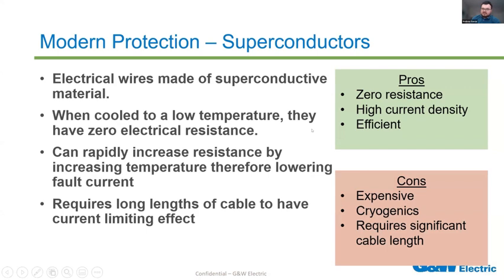So a fraction of the cable size and weight, you end up using smaller poles, and it ends up being less expensive. But the cons overall are that these are a lot more expensive than a regular conductor. Superconductive material is not cheap. These also add cryogenic hazards to your system.